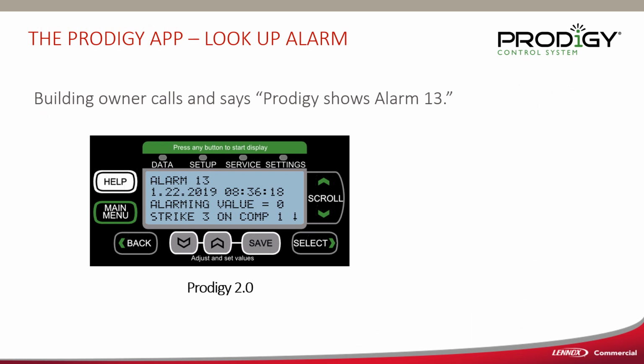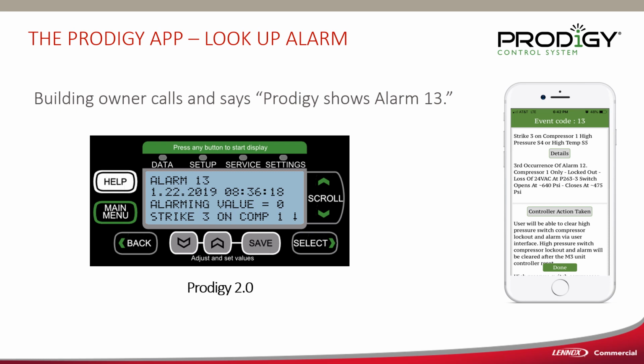So if a building owner calls you and says, hey, I've got an alarm 13 on my Prodigy board in my unit, you can go to your phone, look up and see what alarm 13 is. It's going to tell you it's third strike, because they're all 3 strike before they lock out, so they're automatic reset for the first 3. Third strike, compressor 1, high pressure, and now you know what's going on with that unit. And down below, it's going to tell you what action the controller has taken because of this, and you can then send your technician out. He already knows what he's going out there to look at.